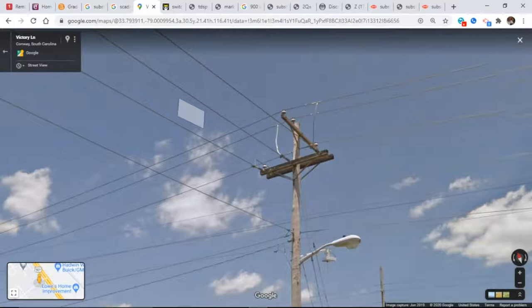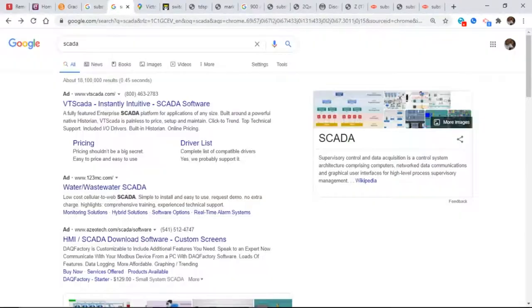Santee Cooper, when I left, had 183 substations. That's a lot of substations. They love to build a substation. And there were, of course, hundreds, if not thousands, of different points inside a substation to monitor. I don't know if you've heard it before, but that's what they call data overload, or information overload. The computers at the main dispatch center are monitoring everything all the time. Only a computer can do it. But once an event occurs, say a problem occurs, it takes priority over all of that information gathering, and it alerts the dispatcher of what's going on. So it is a really sophisticated system.